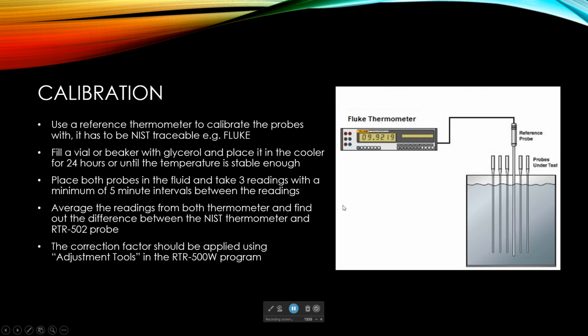One of the key factors for setting up this instrument in the lab is that it has to be accurate. To document the accuracy, we need a highly sensitive thermometer calibrated by NIST or NIST traceable. We take the same vial or beaker and put in the probes under test and the reference probe. The most important part is to let it stabilize so there won't be differences, and it should be in an isolated, stable environment.